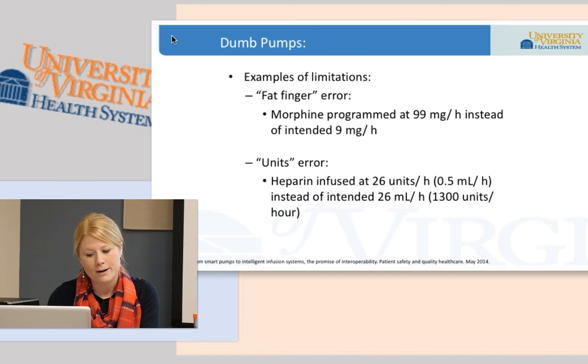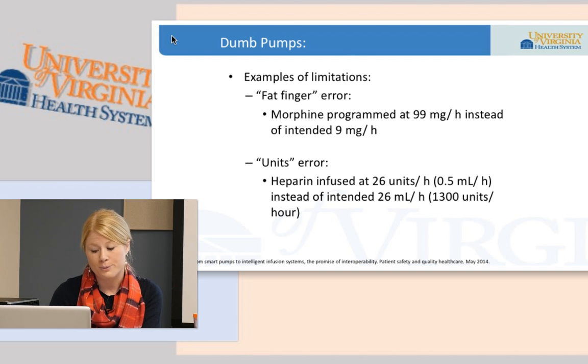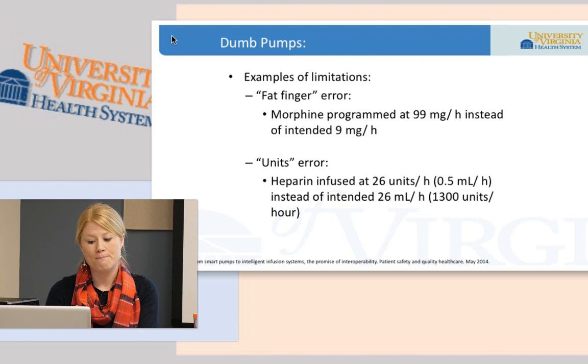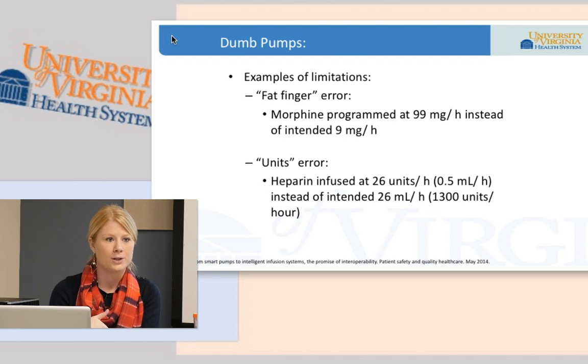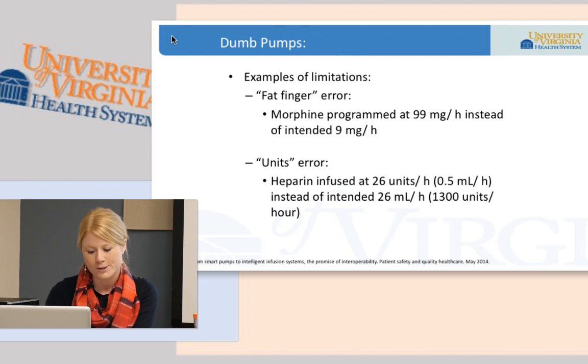There was also the units error, so things were being infused in units per hour instead of milliliters per hour, or vice versa. An example with heparin, which would not be ideal for any clinical situation, would be 26 units per hour being entered into the pump, which is really 0.5 milliliters per hour, instead of 26 milliliters per hour, which is what the intended dose was of 1,300 units per hour. So some pretty significant errors were occurring, and there wasn't really a catch function in it, but keep in mind that there were additional safety features available that weren't previously available, so it was kind of a give and take for these pumps.